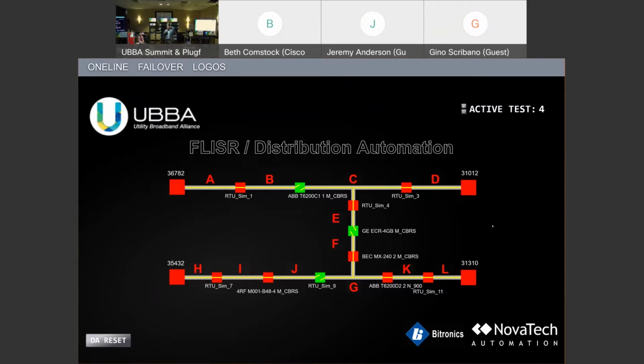If we are not well coordinated, anybody know what coordination means in electrical system function? We have to set that time and that overcurrent value. So that makes a curve. And you want to stack those curves, and ideally, they stack such that the one closest to the fault operates first.